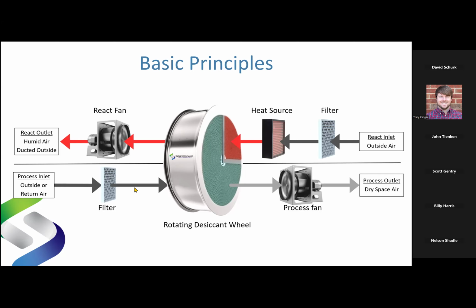Now I do have two airstreams. We will talk quickly about this upper airstream and then I'll come back to it. This is my oven. This is how I dry it out. Okay, we'll come back to that in a minute. On the lower portion of this drawing is what I'll call my process airstream, or the airstream that I want to dehumidify. Now, in the center of these two airstreams opposing one another, never letting these two airstreams come in contact with one another based on seals, right?